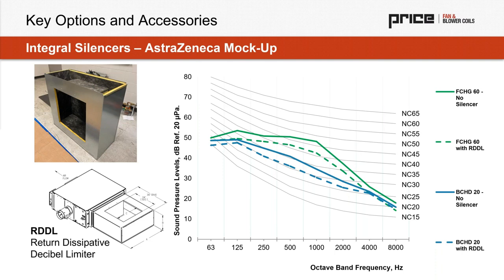So the best option from this mock-up, which tested 8 different configurations of product with different attenuation options, was the direct drive blower coil, which was measured at a sound pressure of NC31, expected to be closer to NC28 for 1400 CFM, fully open ceiling, and no external duct wrap at all. So just raw product with an attenuation option from the manufacturer, 1400 CFM and only NC28.